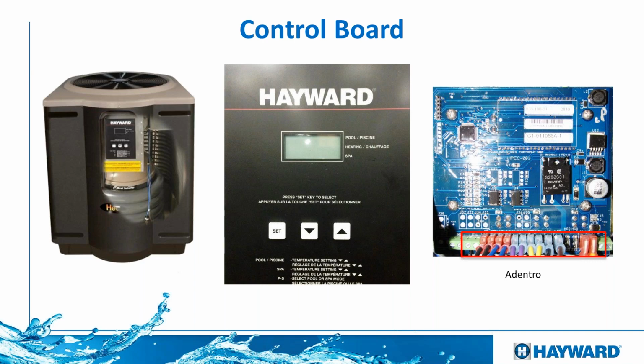On the inside, we have a bottom part where we have a whole bunch of wires. The first little bar that we see here on the left side is labeled WS, which means water sensor, and DS, which is defrost sensor. So those are the 2 sensors that we have inside of the heat pump. The water sensor is the one that detects the temperature of the water, and the defrost sensor is located inside of the coil to detect when the heater is getting very cold. Before it freezes, it will shut off the heater, and maybe it will turn on the fan to defrost the heater. So it's part of the safeties.